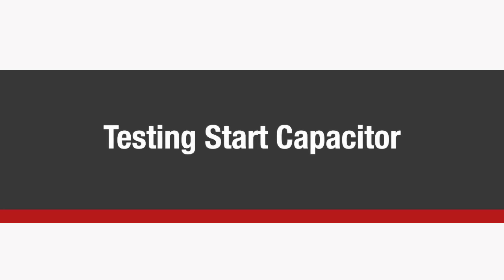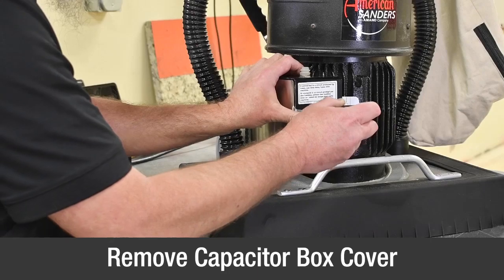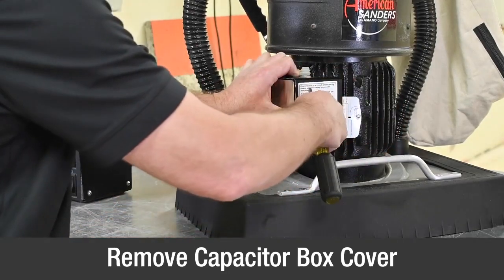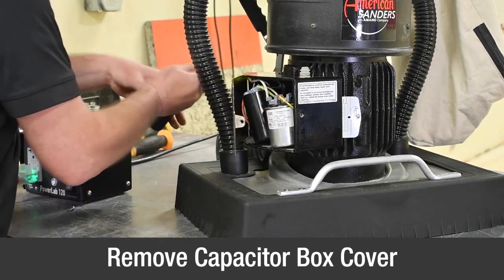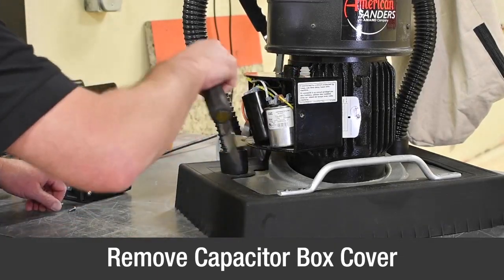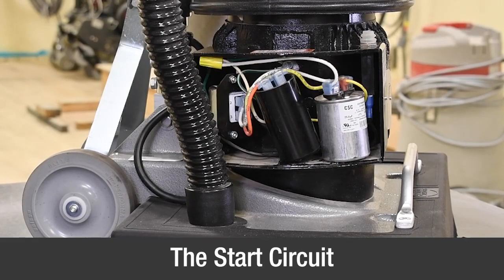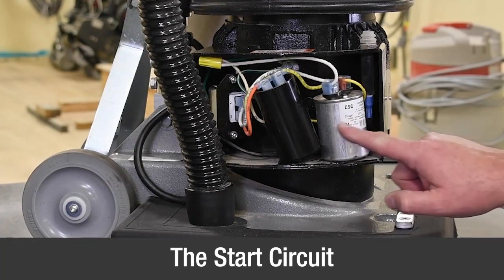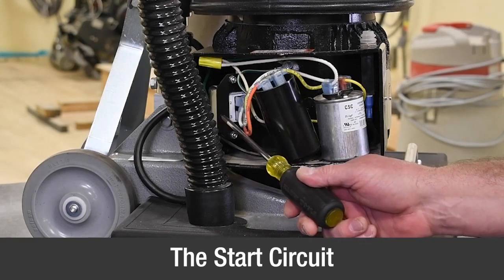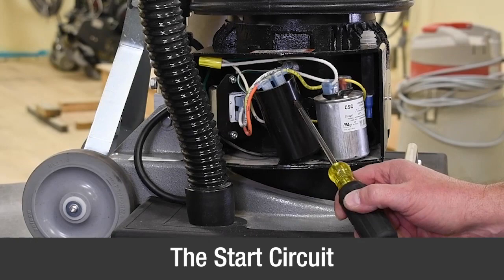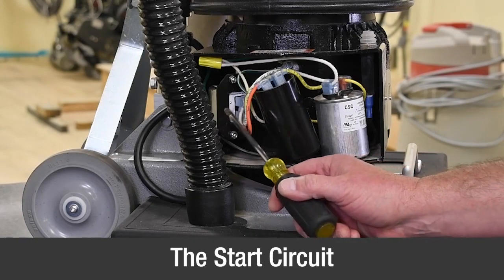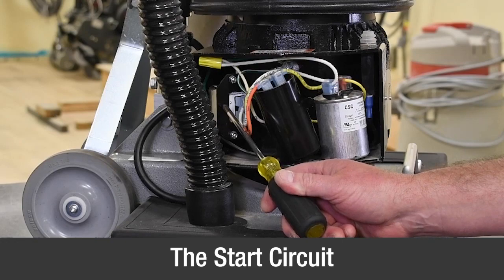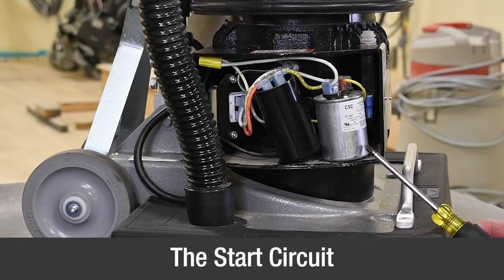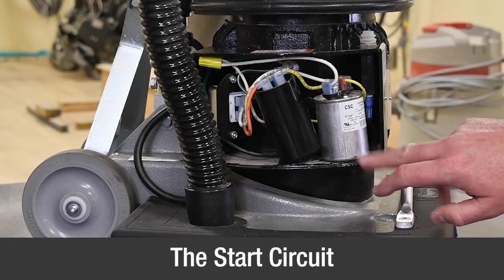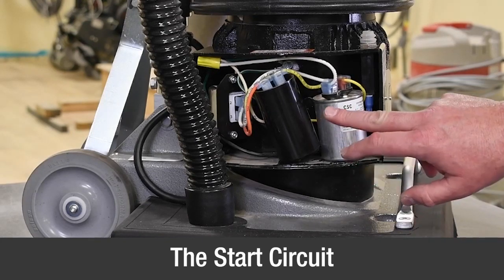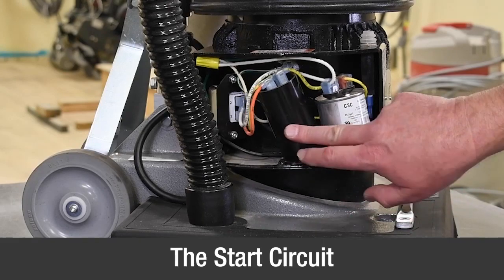Start capacitor testing. Remove the cover of the capacitor box on the side of the motor. Inside the electrical box is the 15-amp circuit breaker, run capacitor, start capacitor, and start switch. These components make up the start circuit. The start capacitor is only used to start the motor spinning. The start switch will then disconnect the start capacitor and current will run through the run capacitor while the machine is running. Run capacitors are always in a metal, oil-filled housing. Start capacitors will have a plastic housing.